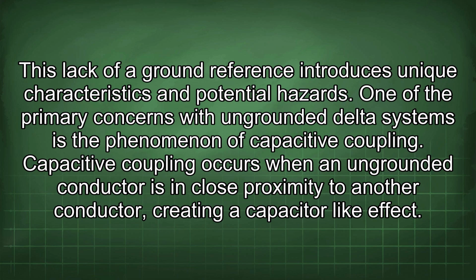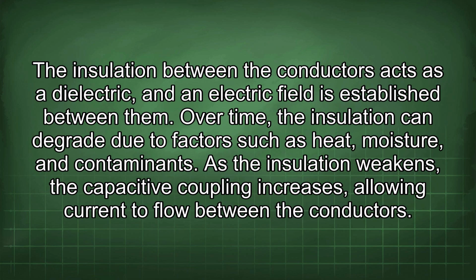This lack of a ground reference introduces unique characteristics and potential hazards. One of the primary concerns with ungrounded delta systems is the phenomenon of capacitive coupling. Capacitive coupling occurs when an ungrounded conductor is in close proximity to another conductor, creating a capacitor-like effect. The insulation between the conductors acts as a dielectric, and an electric field is established between them. Over time, the insulation can degrade due to factors such as heat, moisture, and contaminants. As the insulation weakens, the capacitive coupling increases, allowing current to flow between the conductors.